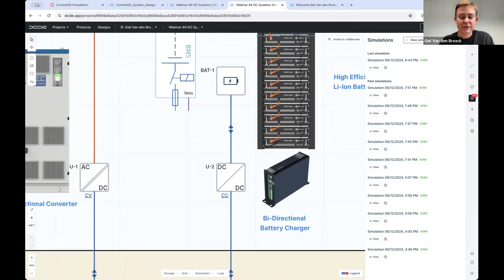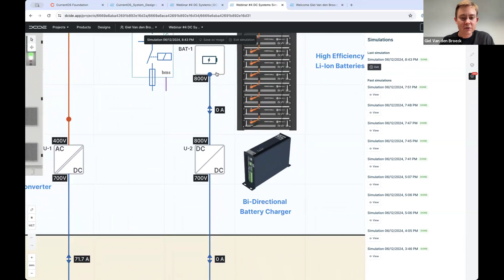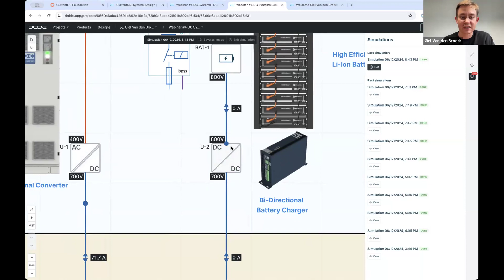the current example, I have my active front end, which is configured into constant voltage mode. So that's maintaining 700 volt. And you see my battery system is not yet active in this case because it's operating in constant current. So I just send the current set point of 0 amps to that battery. Let's say that we want to have both of these units operate in parallel and together maintain a stable 700 volt DC bus.